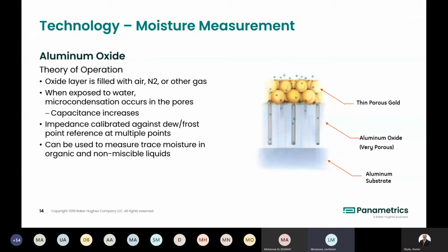So the aluminium oxide sensor basically acts like a capacitor. It's got 2 electrodes and an oxide layer that is filled with air, nitrogen, and other gas. When exposed to water vapor, microcondensation occurs in the pores, and therefore the capacitance in the sensor increases. This capacitance is calibrated against dew frost point references at multiple points. So it's not a linear function. It's more an exponential. So we don't do a 0 and span calibration. We do a multi-point calibration from about 14 points of measurement.